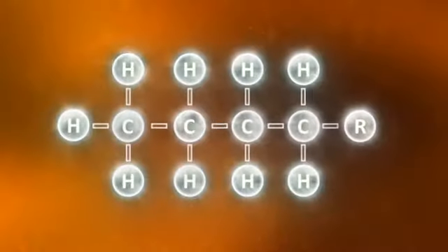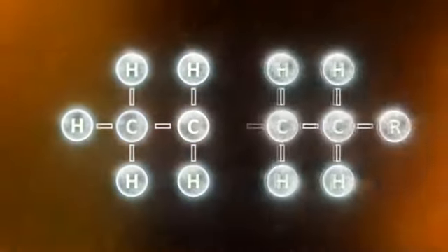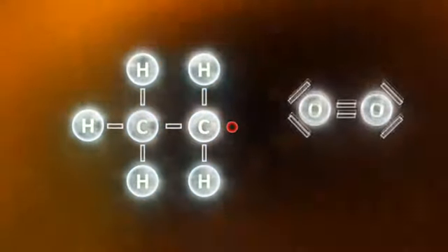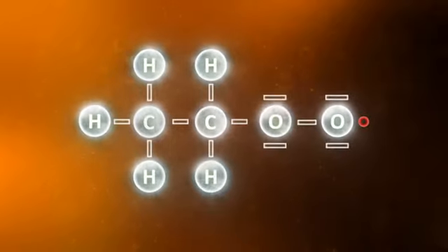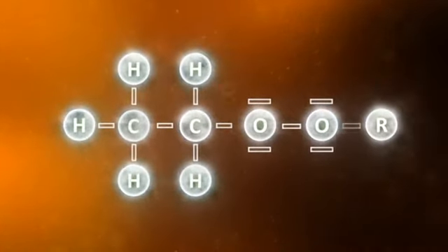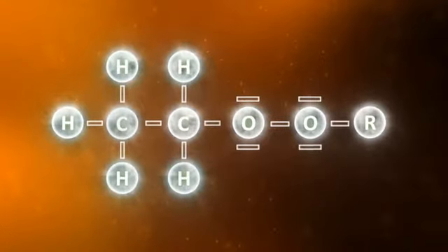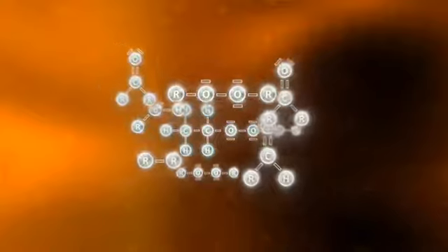Discharge is not only harmful to components, it can also destroy hydraulic oil. The spark discharge breaks up the molecules, and this creates free radicals. These radicals are highly reactive. This means that they will bond with the first molecule they find, as shown here with an oxygen molecule. As a result, the molecules keep getting bigger.